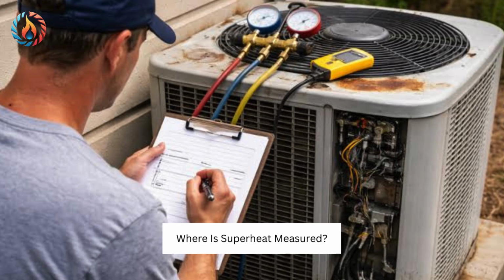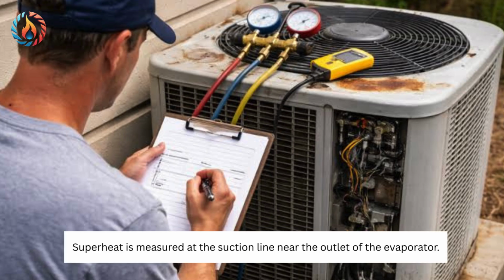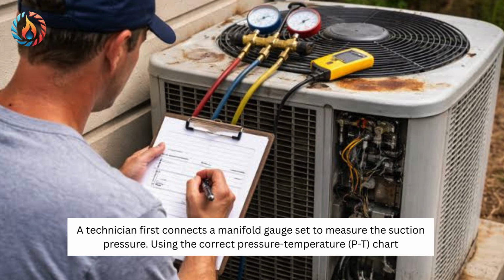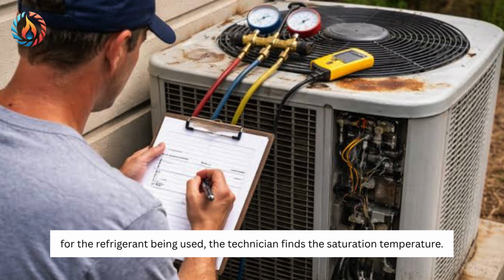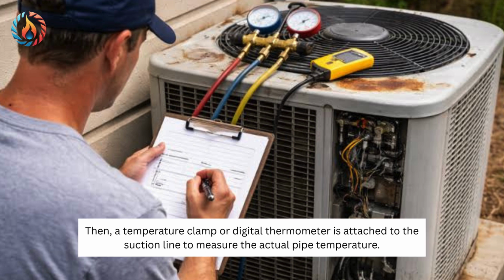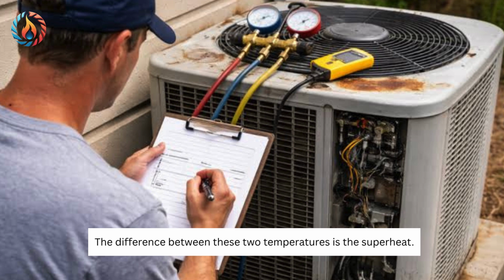Where is superheat measured? Superheat is measured at the suction line near the outlet of the evaporator. A technician first connects a manifold gauge set to measure the suction pressure. Using the correct pressure temperature chart for the refrigerant being used, the technician finds the saturation temperature. Then a temperature clamp or digital thermometer is attached to the suction line to measure the actual pipe temperature. The difference between these two temperatures is the superheat.